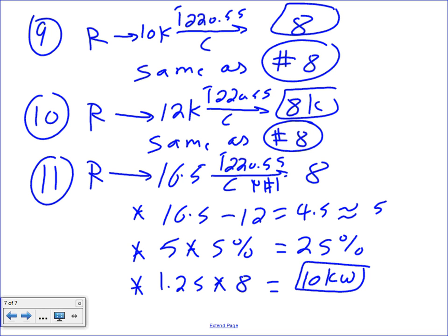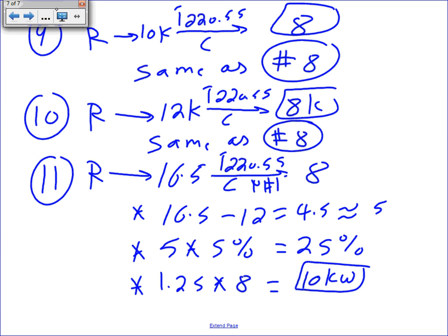Any questions about this? We apply the rule for the branch circuit. Why? Because note number 4 tells us that you can use the demand table for branch circuits too. So number 10. What do I need to do now? Do the whole calculation based on number 10. I'm going to do it right here, just to finish this one in this corner, using red. I equal 10 kW divided by 240. What would that give me? 10,000 divided by 240 gives me 42.